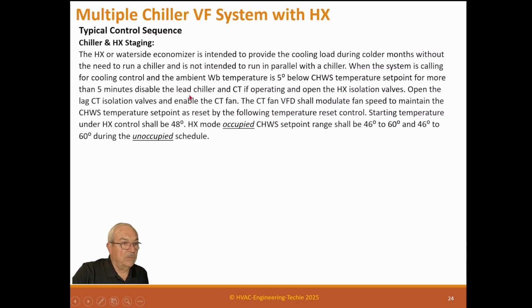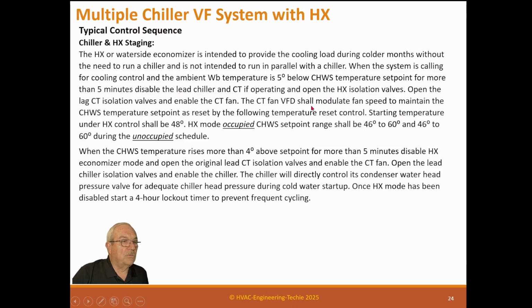High altitude, I had a plant at 7,000 feet, and I could run the plant 9 months of the year just on the heat exchanger. The few summer months, the 3 summer months I couldn't, but the rest of the year, this is a manufacturing plant, so we had heat load the entire year. So these do work.